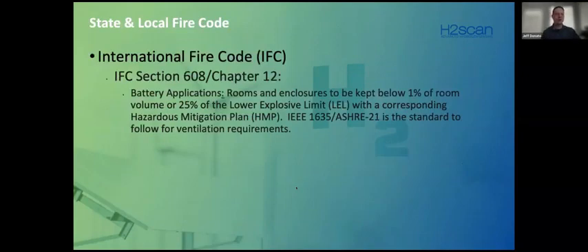When we talk about codes, the ventilation codes typically are developed through a couple of organizations, the International Fire Code and the National Fire Protection Association. The language is fairly similar, and it would be IFC section 608 for some of the older codes that are still adopted. The newer version is chapter 12. In this case, they both say that battery rooms or enclosures need to be kept below 1% of room volume, which is 25% of the lower explosive limit. This needs to be part of your hazardous mitigation plan. Hazardous mitigation plans can be anything from controlling your ventilation to adding detection, as well as detection tied into gas purge systems, so the fans will kick on when it starts reaching 1%.